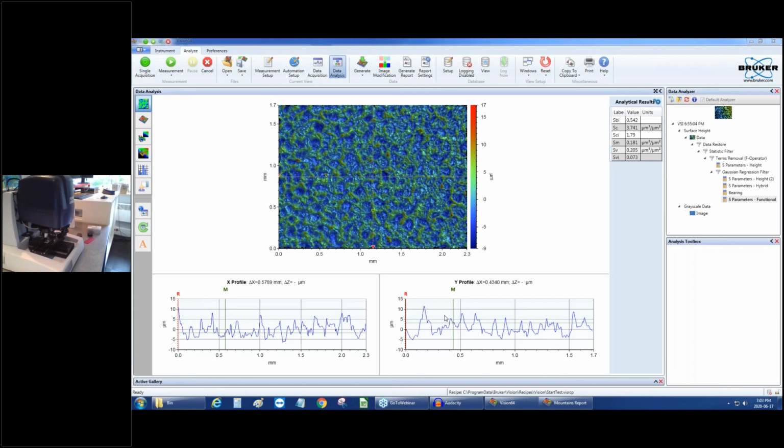But whenever you have a process in place where you have a good clue that roughness could play a role, definitively the new areal norm provides foundations for you to measure and even quote and spec on technical drawings some of the parameters we use. And for instance, the optical profiler is a quick way of having a non-contact, fast, and very precise technique to measure surfaces and then extract valuable information for texture.